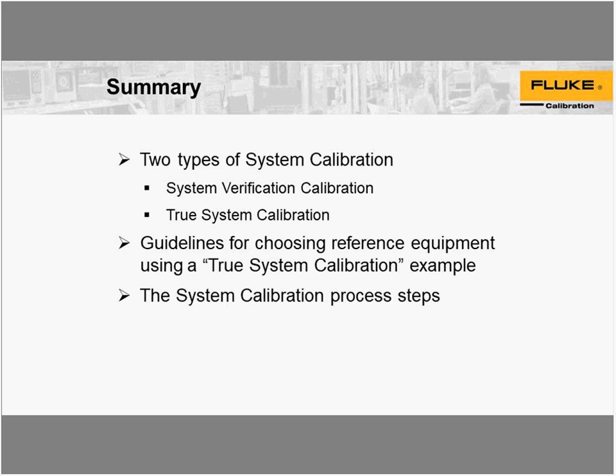Exactly, to me it's like metrological traceability. So I'm thinking it's a typo, but metrologically speaking, traceability is tracked from a reference standard, a known intrinsic standard, transferred to, for example, an intrinsic standard such as a fixed point cell, which all of our reference SPRTs are met with a full set of fixed point cells. That intrinsic temperature is transferred by standards to that reference SPRT, and the reference SPRT now carries the backing of intrinsic standards, and then that is transferred to your DUT or UUT by means of comparison calibration.